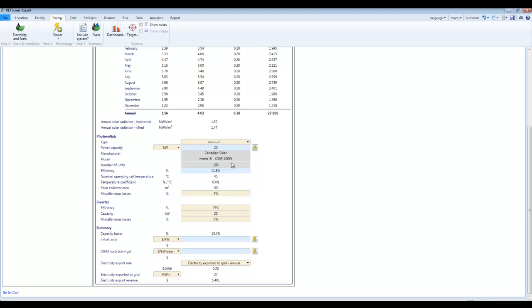Another thing to realize, you may find that you can't find the module that you're thinking of using over here in the product database. Guess what? It doesn't really matter as long as you pick a module that has the same wattage. Yeah, sure, the efficiency might be different on the one that you've picked, but a 200-watt module always produces 200 watts in standard sunlight conditions. It doesn't matter how efficient it is. What changes with efficiency is physically how large is that module, that 200-watt module. A very efficient one will be physically smaller, a not so efficient one will be physically larger, but they're all going to produce 200 watts.